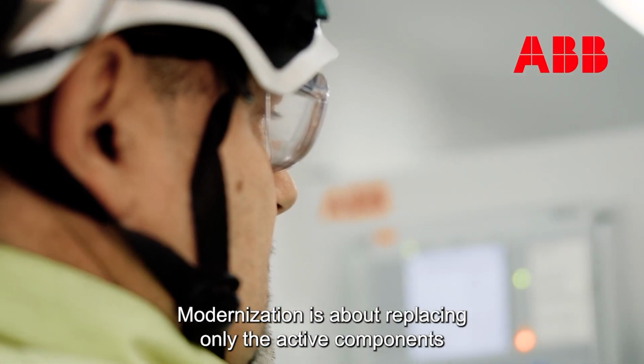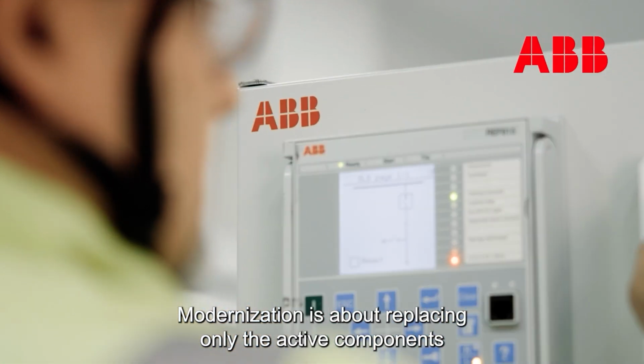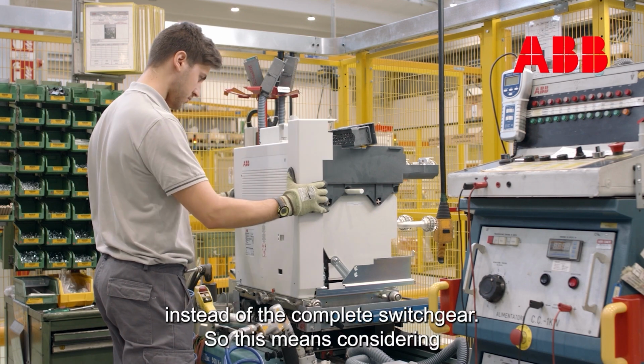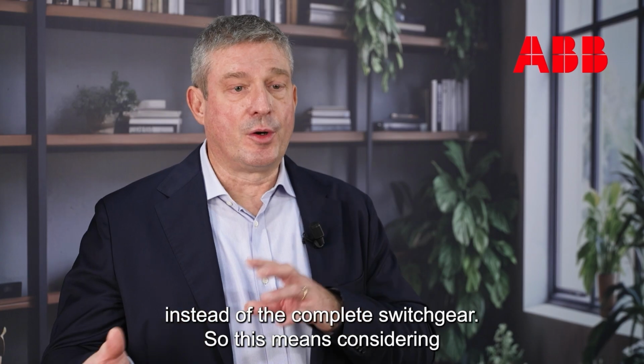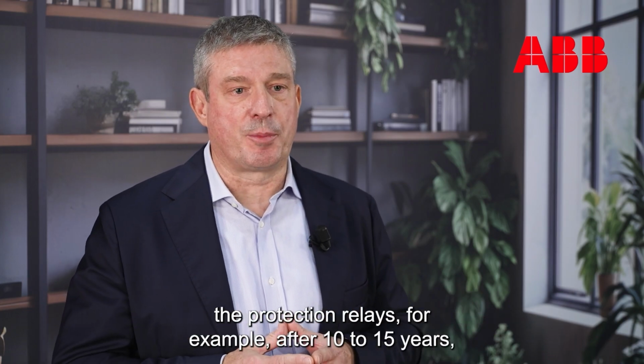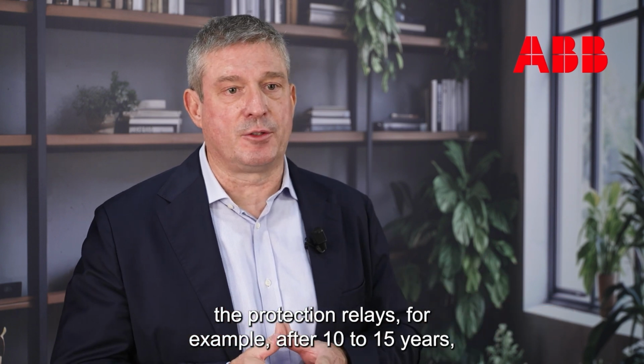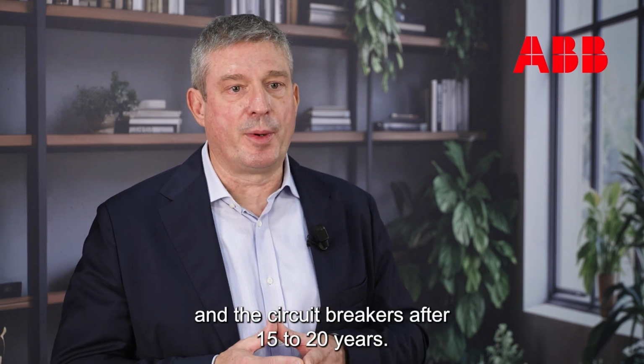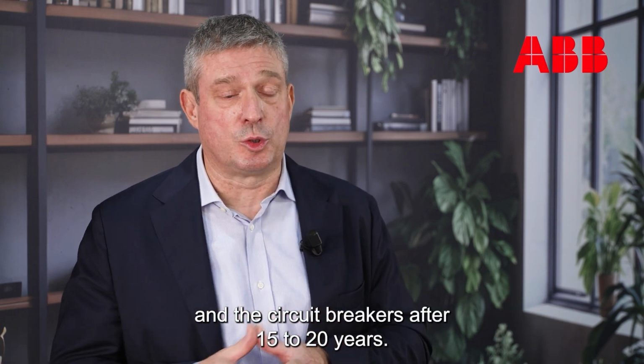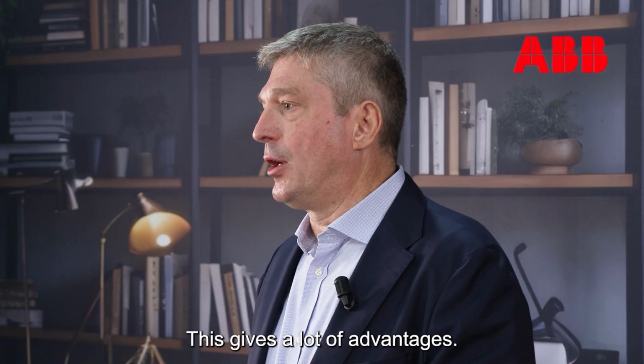Modernization is about replacing only the active components instead of the complete switchgear. This means considering replacing the protection relays, for example, after 10 to 15 years, and the circuit breakers after 15 to 20 years. This gives a lot of advantages.